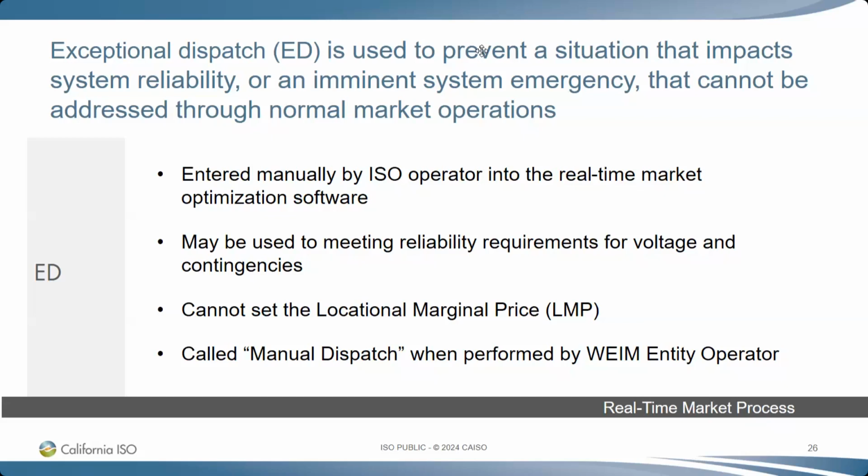So I do see a question. Yes, thank you, Heidi. Yeah, go ahead, Drew. Yeah, this is Drew Thompson. I'm a Gen dispatcher here at the California ISO. Greg had a follow-up question in regards to a verbal ED. So you are correct, Greg. There will be a lag time between a verbal ED and your ADS instruction coming into play. As you know, the market is a 5-minute market. So if we give you a call and we give you a verbal ED, the expectation is that we'll give you a set time. So we'll tell you either immediately and we'll state the time. So if I gave you a verbal exceptional dispatch as of right now, I would say immediately at 10:03, you follow this exceptional dispatch, and I'd give you that instruction. So there could be a lag time between the verbal ED and your ADS instruction, but that's to be expected in that verbal kind of context. Hopefully that makes sense.